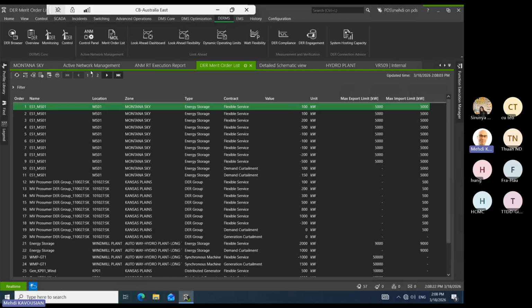So what if we create a merit order, for example with a value of 100, and in some cases we just need about 50 kilowatt only? Could we use this but just for 50? Yes, that's actually a good question. So first, if 100 is too much, it divides it by two. So 50 is okay, use 50. If 50 is not okay, go to 75 in between. So it tries to put only as much as is needed.